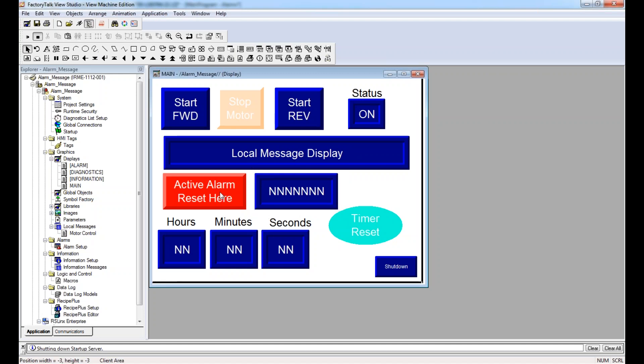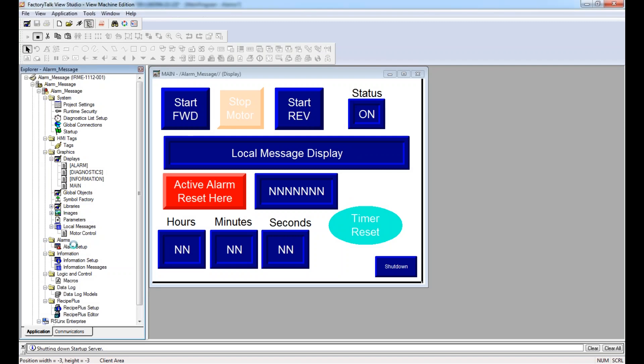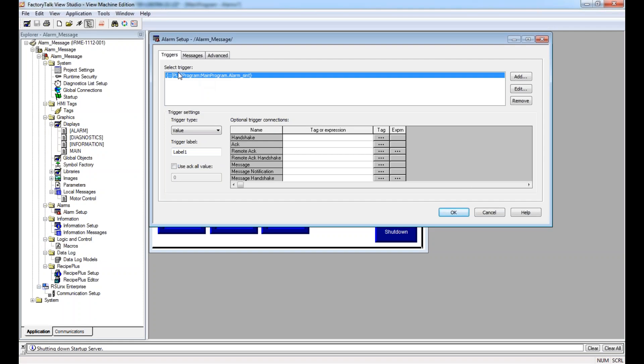This is the timer reset. But here's an alarm reset. Now, you may think - and I will go in to show you how to do setup alarms - that I can physically clear out alarms with my physical alarm acknowledgement. There's no way of doing that by default, because obviously, if I'm just clearing the alarm, acknowledging alarm, I should have different steps to then actually go fix the alarm. Does that make sense? And this active alarm reset here button will show me, it gives me another step to reset. Because if you look over here, under alarm setup, I have linked my alarm with my alarm sent, which is the value that gets changed if I have an alarm. This works just like local messages, except it's already tied up into the alarm menu, and it's going to show up over everything when I actually run the process.